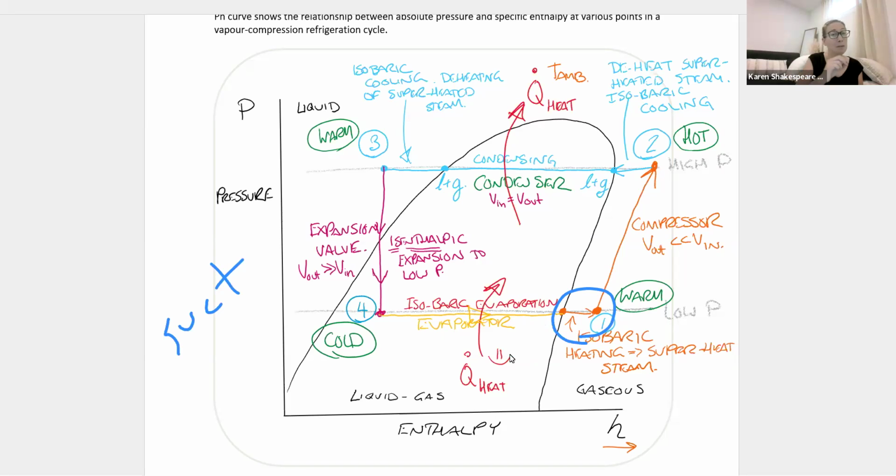And the evaporator has to be sized such that the suction line is going to bring you into pressure below ambient. It's going to bring it into a vacuum so that you're up here in superheated steam, so that you know that you are bringing a gas into the compressor so that you're not compressing any liquid. All right, so those are important elements so far.